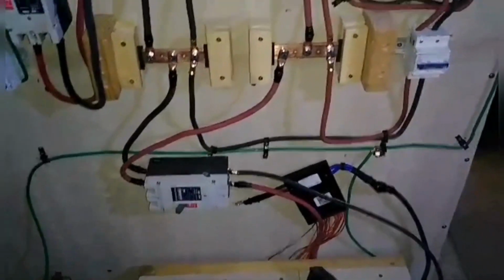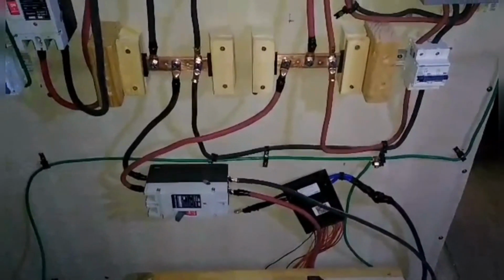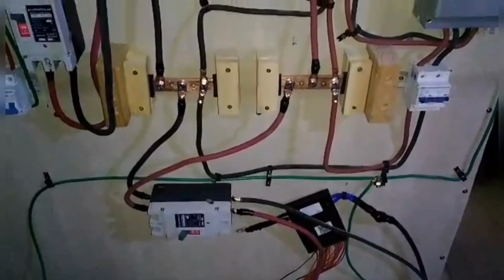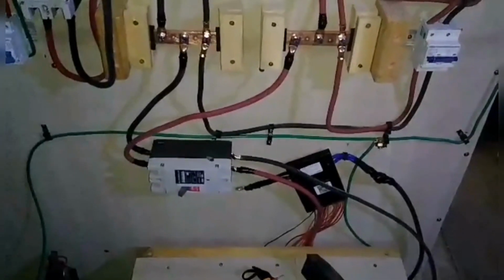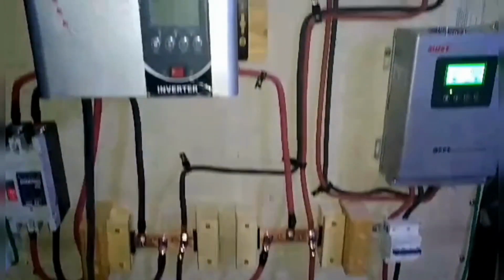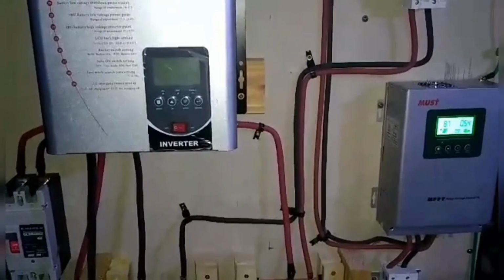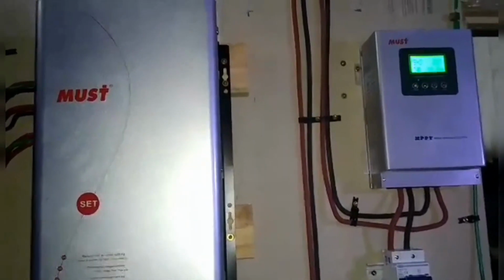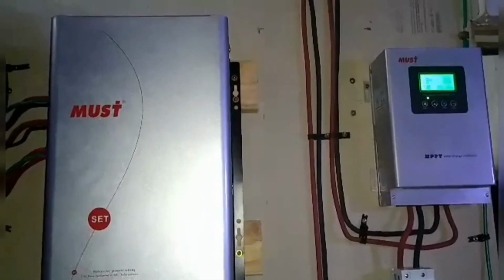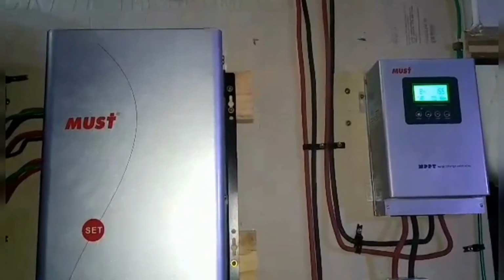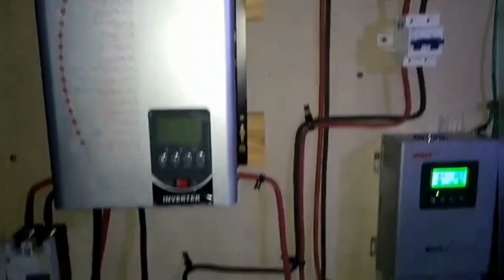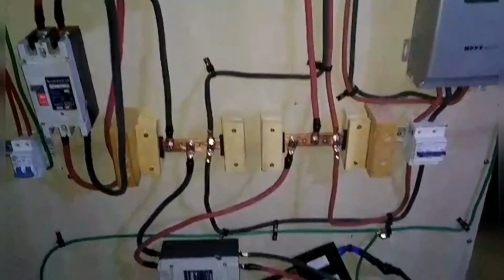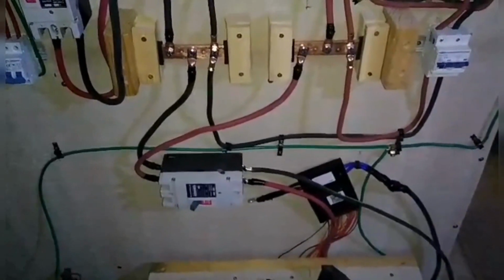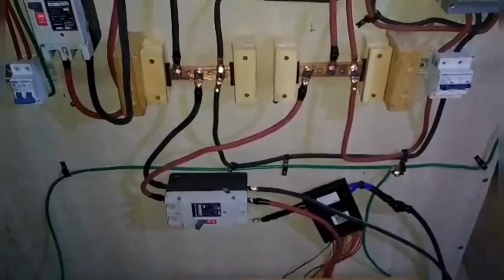I did run into an issue with the BMS. According to the manual, it takes a 5-volt differential between the battery and its inlet in order to start up, which means you have to have the solar panels connected before the BMS will start. That was messing up the order of operations, so I had to bypass it so I could get the charge controllers turned on and set up just on battery power, and then turn on the solar after. So I had to disconnect the BMS in order to get everything turned on, and here in a minute I'm going to give the BMS some power, a higher differential than it wants, so it'll turn on, and then I'll reconnect it.